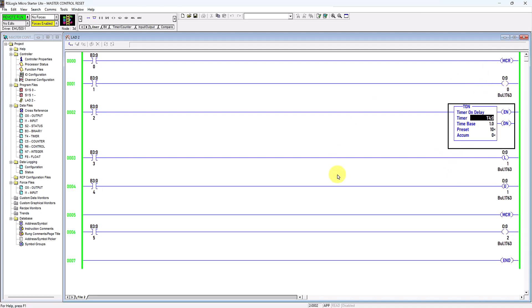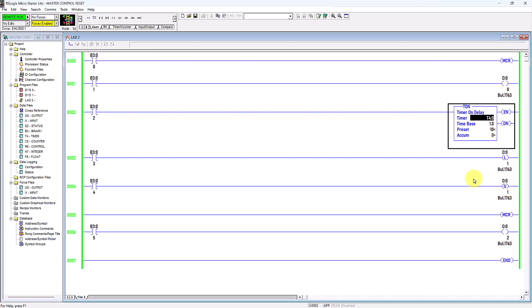After the closing MCR rung, there will be no effect because it is outside the fence zone or control area. Once the MCR instruction is de-energized — like an emergency switch — all the non-retentive outputs in this area will be de-energized. It will only affect non-retentive outputs such as the output coil and timer, but it has no effect on retentive outputs such as the latch/unlatch virtual output coil, counter, or retentive on-delay timer.